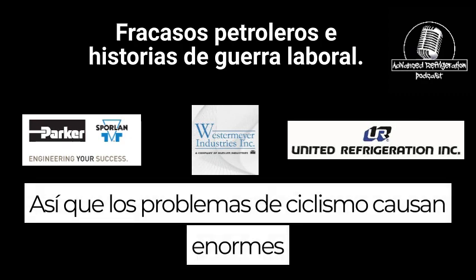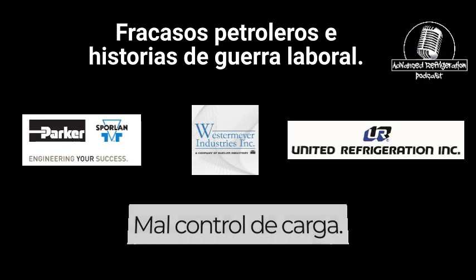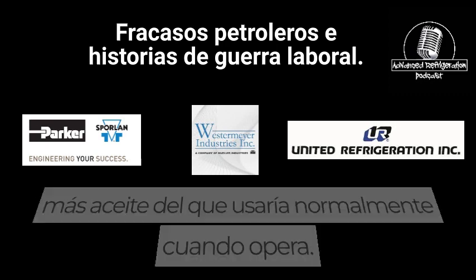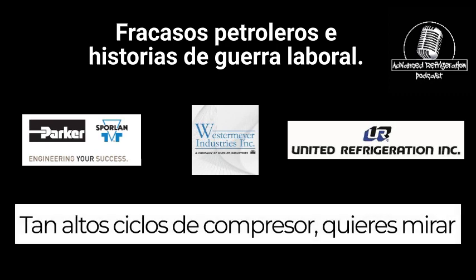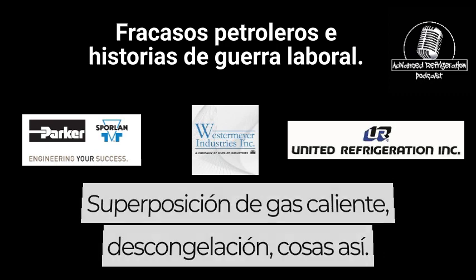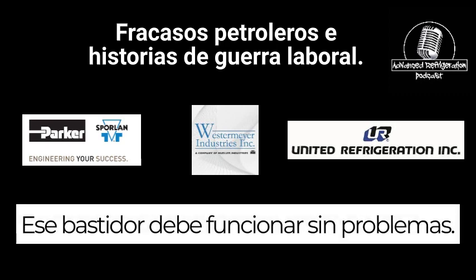Rapid cycling issues cause huge oil problems, meaning load control. Poor load control means high compressor cycles, and every time you start that compressor, you're moving a ton more oil than you would normally when you operate. So with high compressor cycles, you want to look out for compressors that are not operating properly, running high discharge temps, defrost scheduling that's too many at one time, overlapping hot gas defrosts, stuff like that. That rack needs to run smoothly.